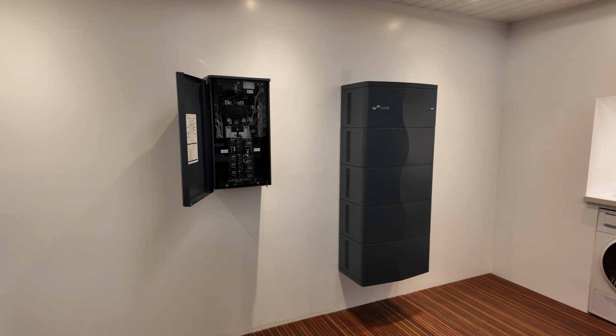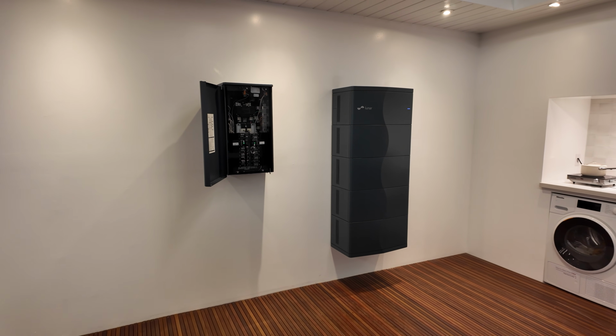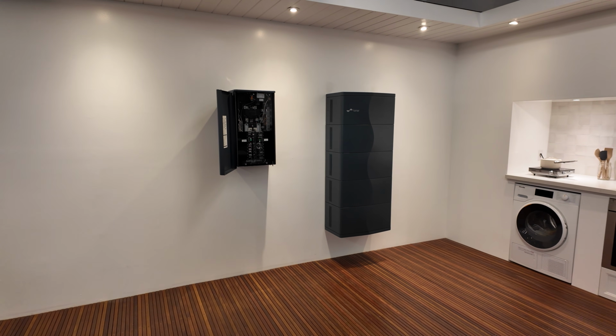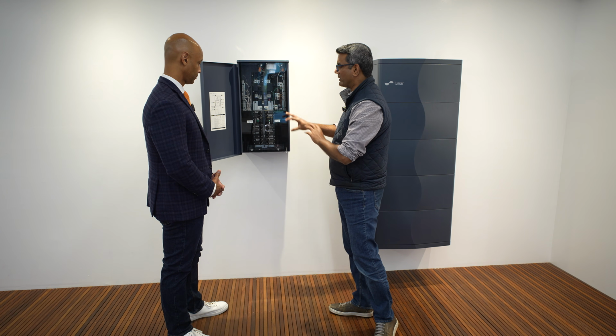Almost all solar storage installations require you to put the breaker in some sub-panel or another. It's very rare to put the breaker in the existing panel because homes are old, breaker panels are full, and people have sub-panels all over. Feedback from the installation community is that you always need some sub-panel, and they love that our bridge already has breaker slots where they can put whatever breaker they want.